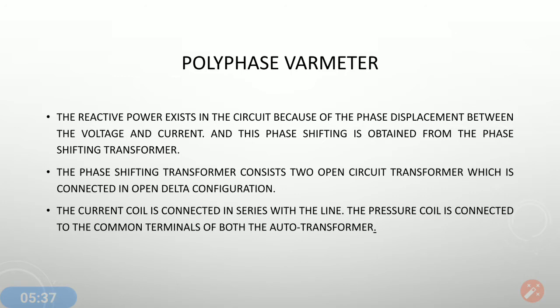The next one is the polyphase VAR meter. We know that reactive power exists in the circuit because of the phase displacement between the voltage and the current, since the in-phase component always produces active power. The reactive power is due to the phase displacement between voltage and current, and this phase shifting is obtained from the phase shifting transformer. The phase shifting transformer of the polyphase VAR meter consists of two open circuit transformers connected in open delta configuration. The current coil is connected in series with the line and the pressure coil is connected to the common terminal of both transformers.